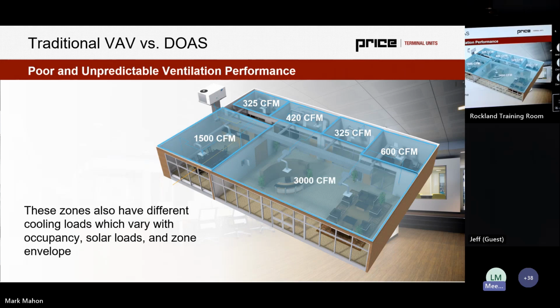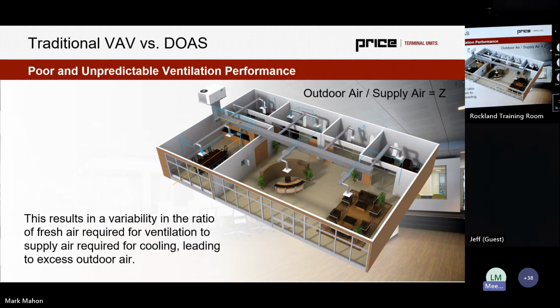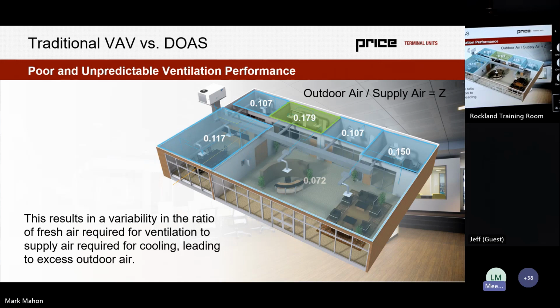And where ASHRAE says poor or unpredictable ventilation performance can come from is because we have a variability in the ratio of fresh air for ventilation to supply air for cooling. Now, their claim from a fundamental laid out perspective is this can be a risk of excess outdoor air or overcooling. And that is true, although there's capability to sequence different zones in ways that would reduce that risk. There are ways to optimize the system further. This is very much a cookie cutter design, but it is true.